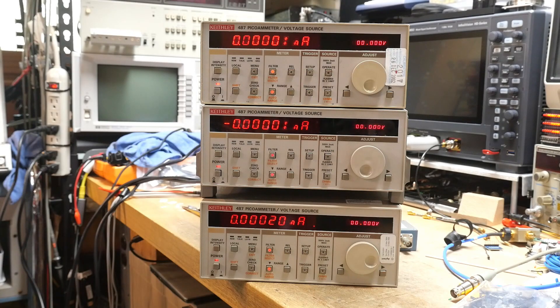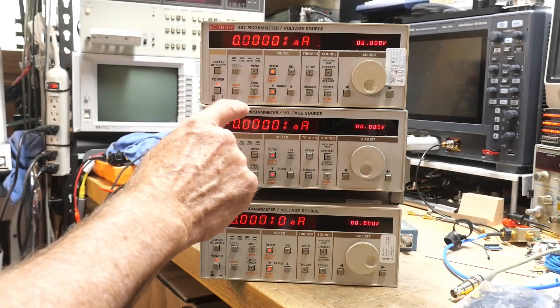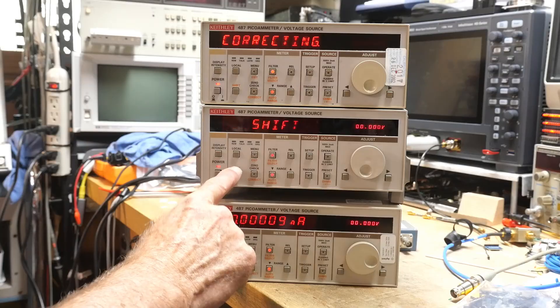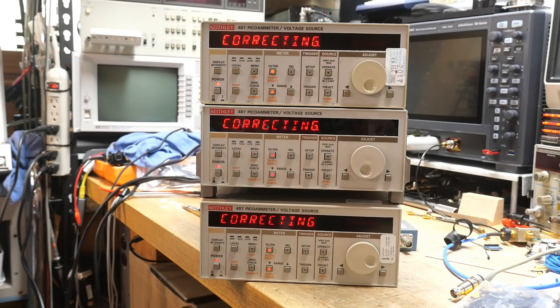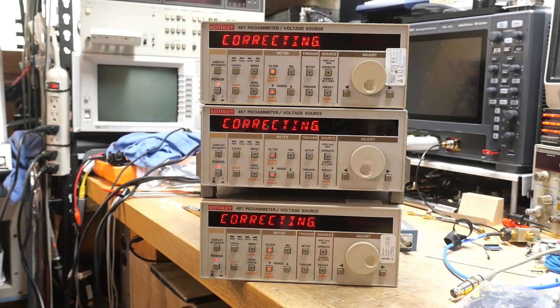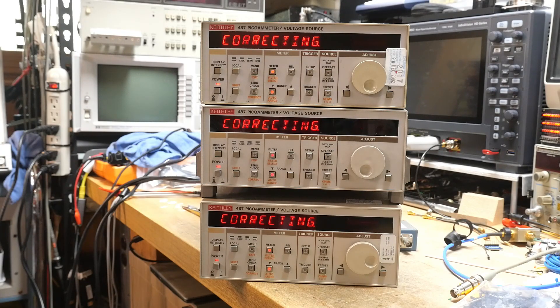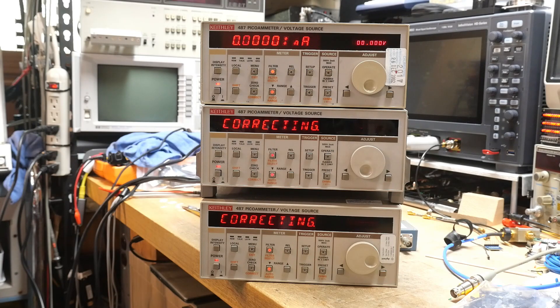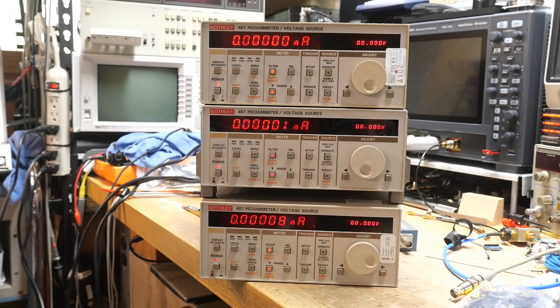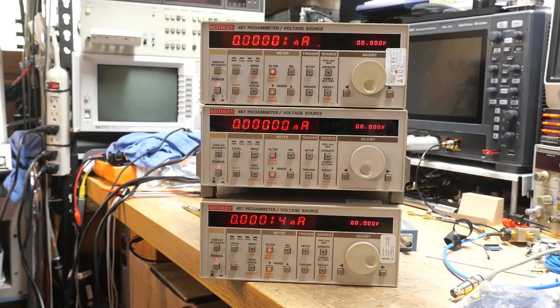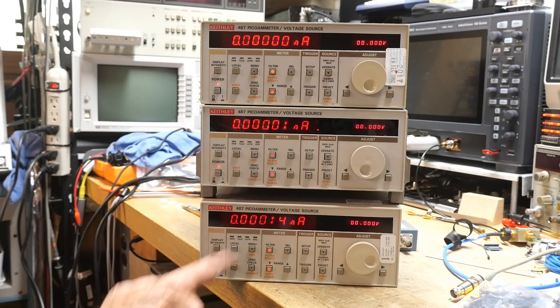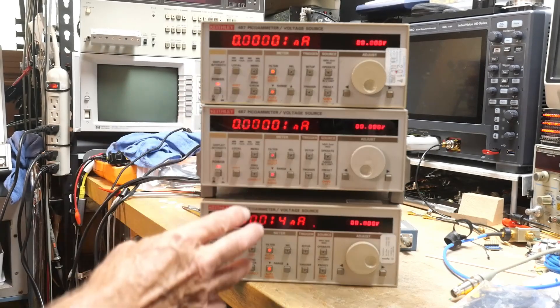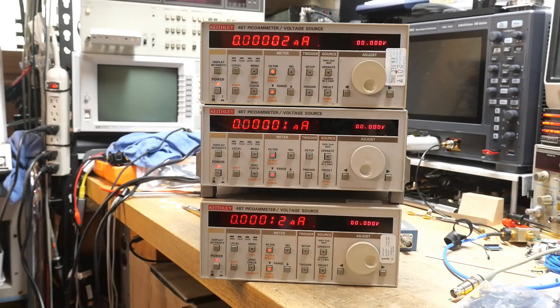Anyway, what we can do is we can do a zero. So we'll do a zero on all of these. And that will correct our zero setting. All right. So they all seem to zero. So this one starts to drift off. This one starts to drift upwards a little bit. All right. So that's one clue here. This one seems to be a little bit funny for zero offset.